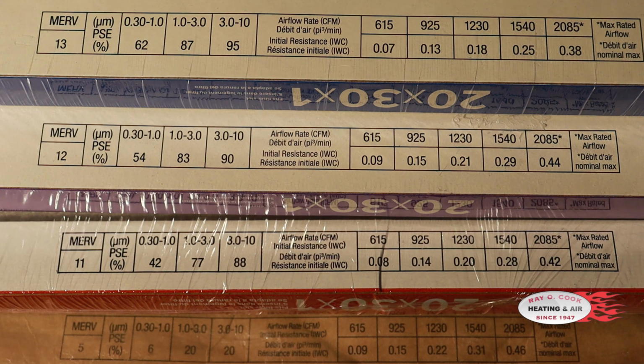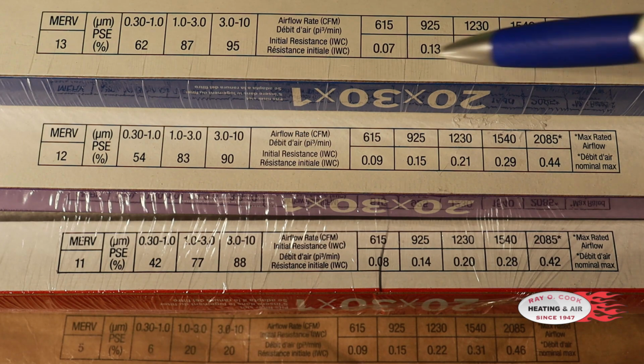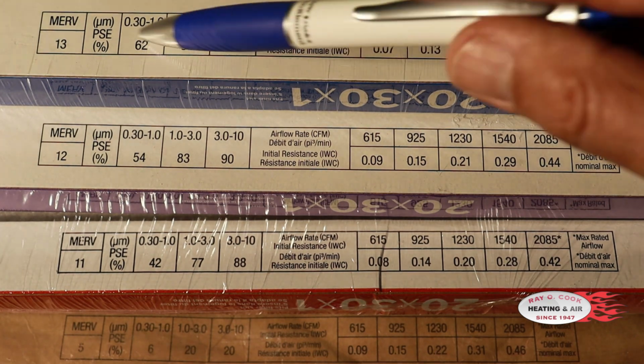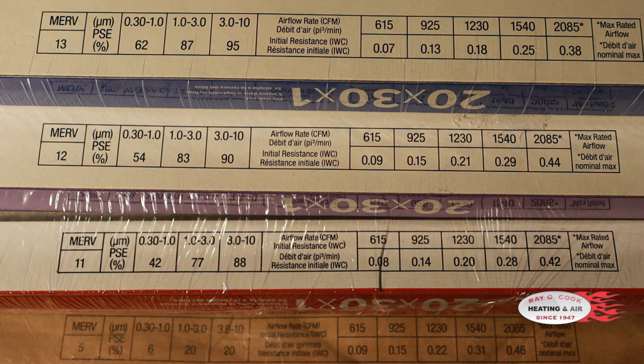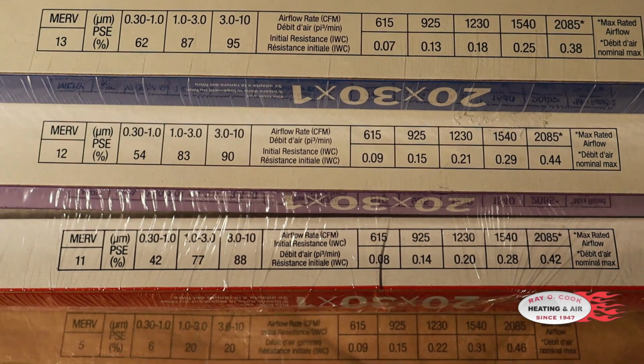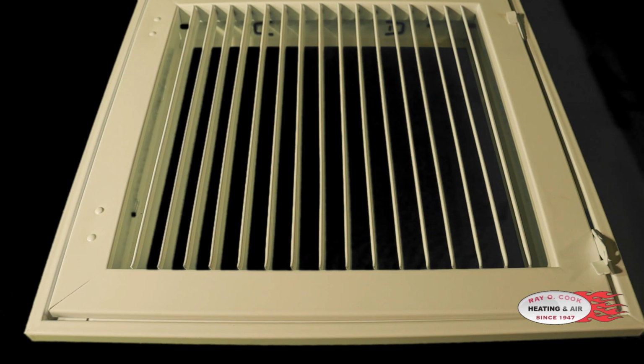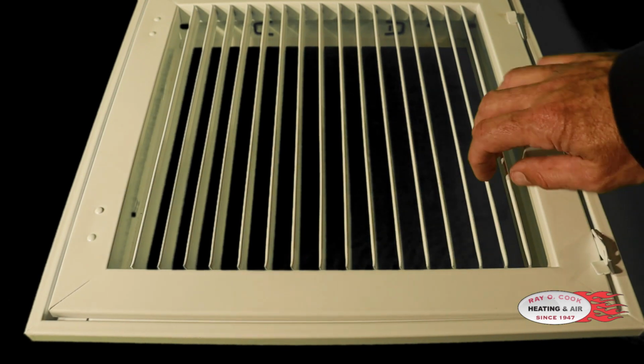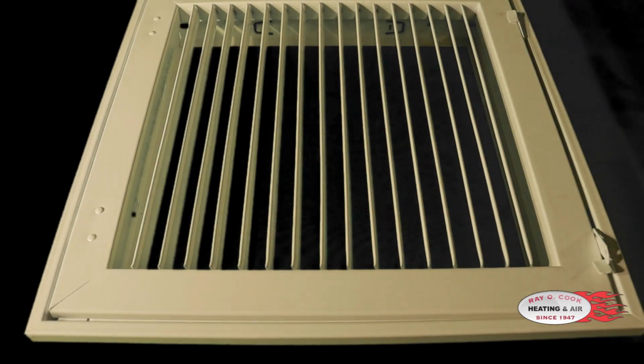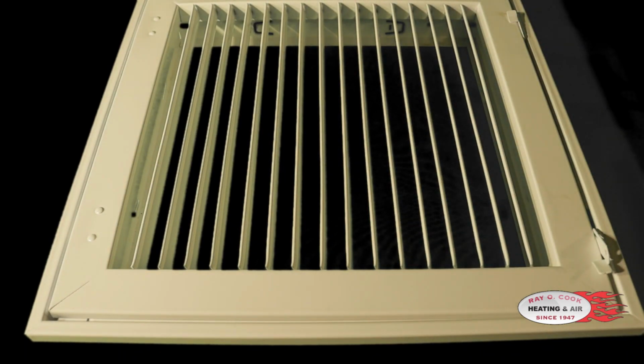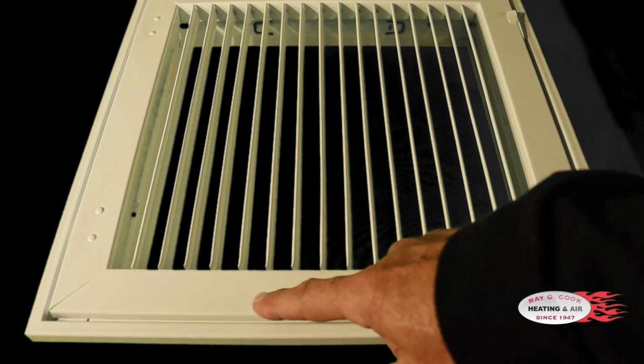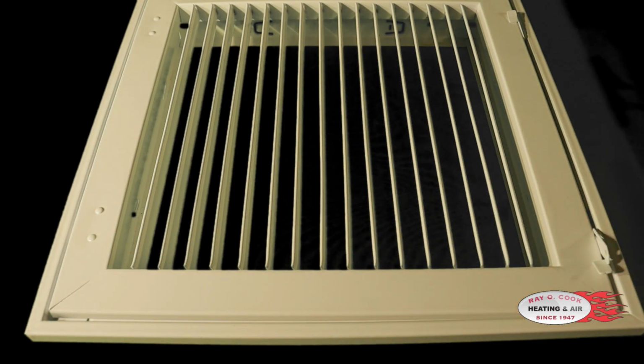most of our surface area, the length times the width of this filter, there's not enough surface area to allow for the loading of the filter, especially on these more restrictive filters that can catch all of these particles. You've got to have a place to put them, and we'll go through that. So basically, this is going to be a filter grill that you'll see on your ceiling. This is what opens where we change our filter, and this is a common issue that we'll see in California with the length and the width of the filter grill not being enough square inches of filter to be able to compensate for the restriction of the filter.